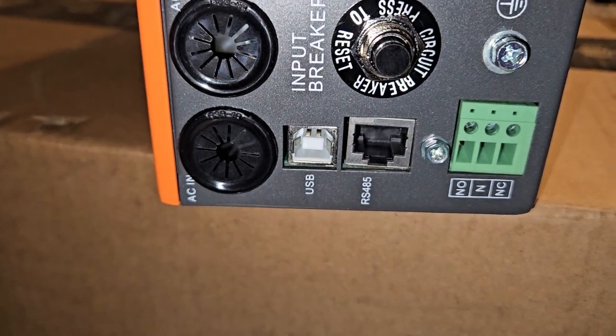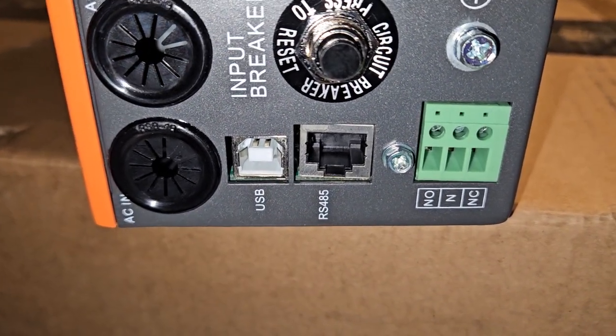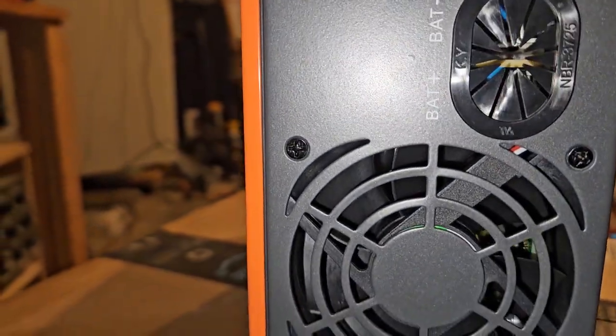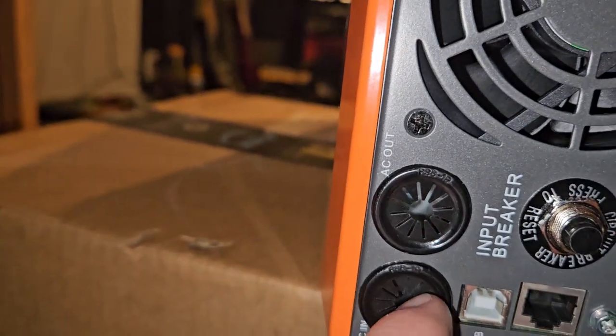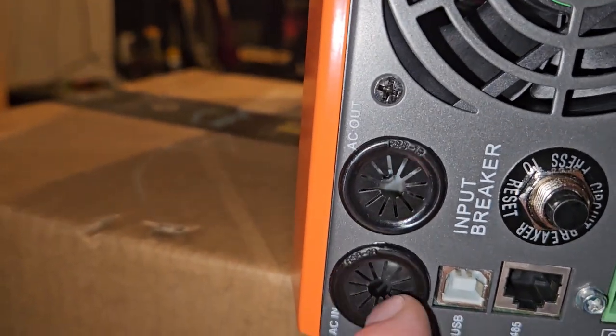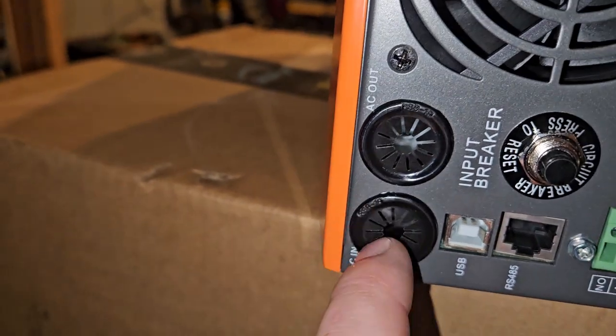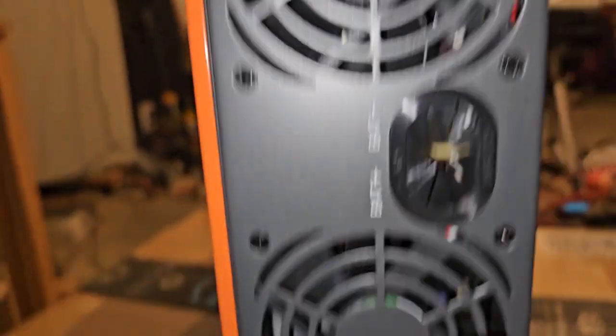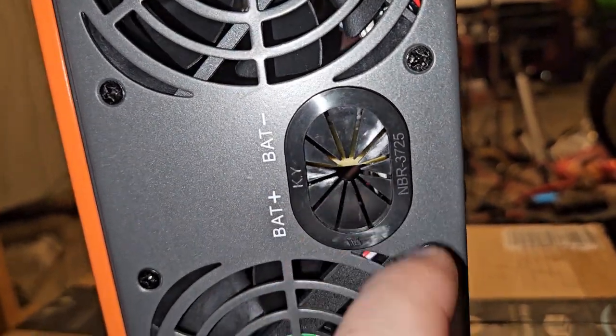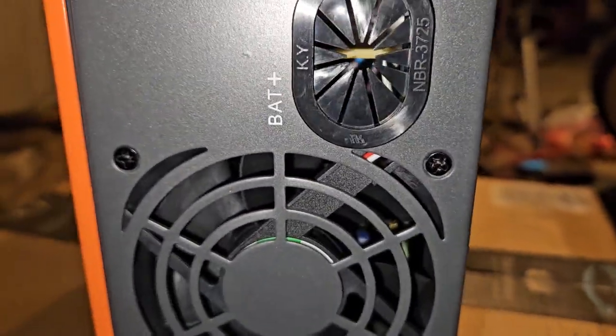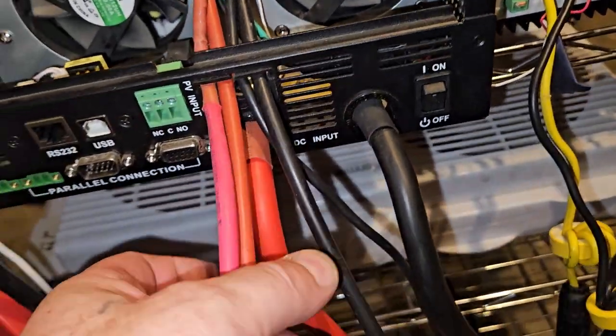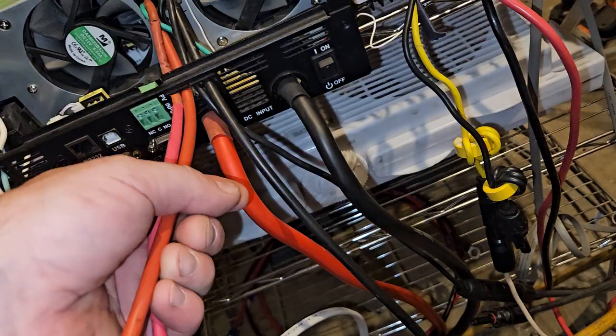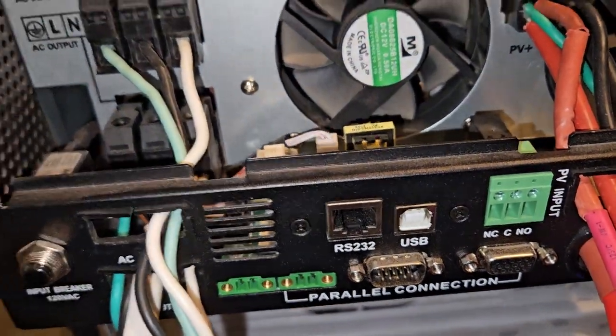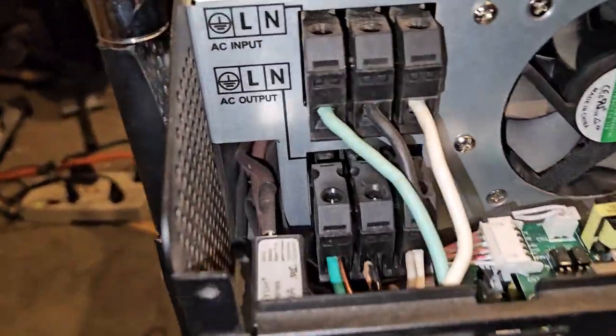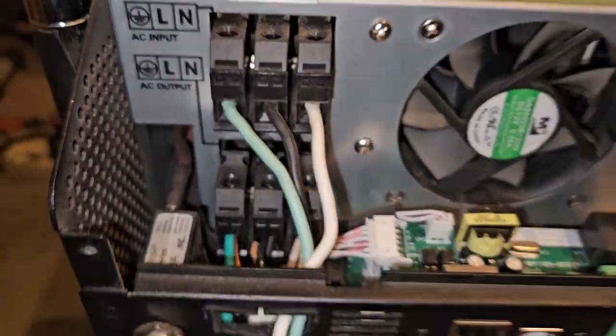Let's see here. We get a USB, RS485, whatever that is, because usually it's called something else. We've got our dinky wires here. What are you gonna put through this? This is ridiculous. I wonder if maybe you can put those round connectors through here. Like, what kind of battery wire are you gonna put through here? I'm using gigantic battery wire, like 2 gauge. And for 24 volts, that's not really important, but look at this one, they barely fit through the hole. And then I've got all my PV, I've just connected it, but if you look at this, this says RS232, and then this other one has some other kind of goofy thing. But you see how there's an earth ground for all of them.